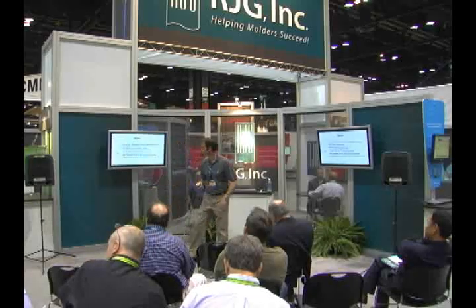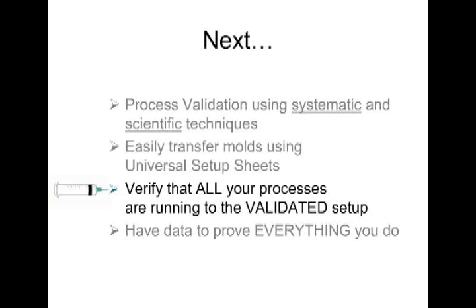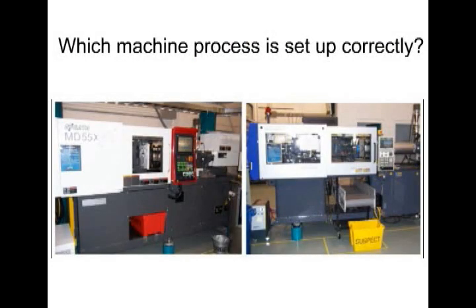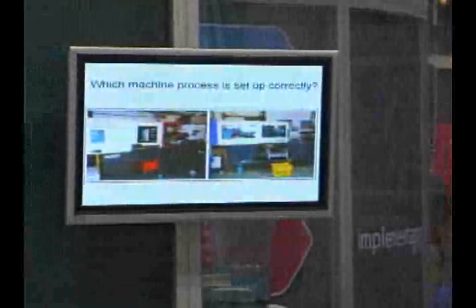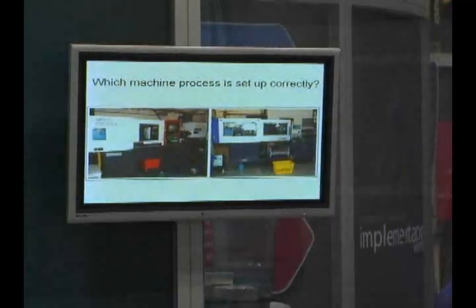Any other questions? Another common problem associated with a medical device is being able to verify whether or not your processes are running to a validated setup. Someone in a production management responsibility type position, operational management, there's always a concern or a need to know whether or not the 24 machines on your production floor are running to the designed process as that mold was as the process was developed. Are you running to that validation standard? There's a number of ways people address this. Sometimes that production manager takes a walk out across the production floor in the morning, wants to get a handle on whether or not the process was running to validated setup overnight.